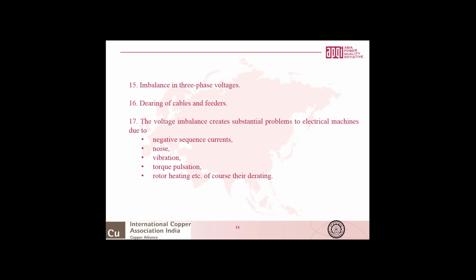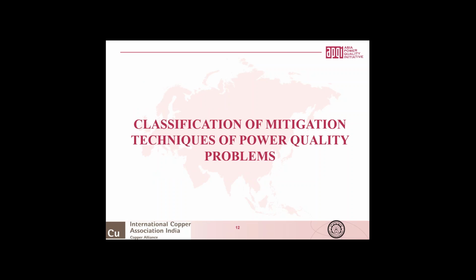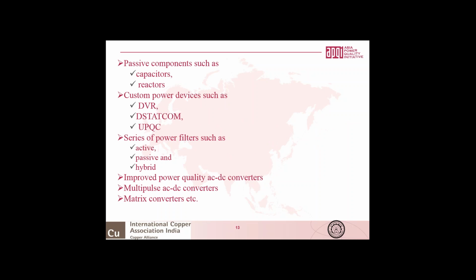The voltage imbalance creates substantial problems to electrical machines due to negative sequence currents, noise, vibration, torque pulsation, rotor heating, and of course, their derating. Well, we can classify these mitigation techniques for these power quality problems broadly into the following categories. We can use passive components such as capacitors and reactors for meeting the reactive power and typically providing load balancing as well as elimination of neutral current under linear kinds of loads.